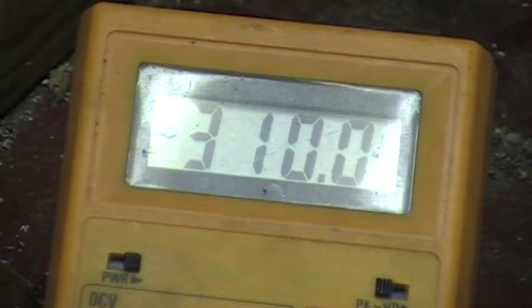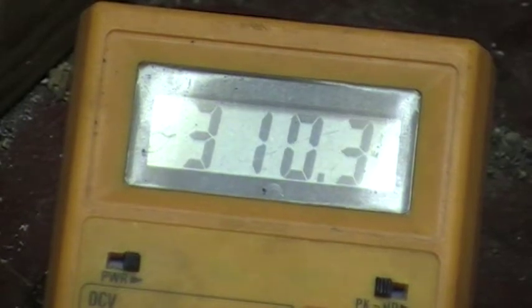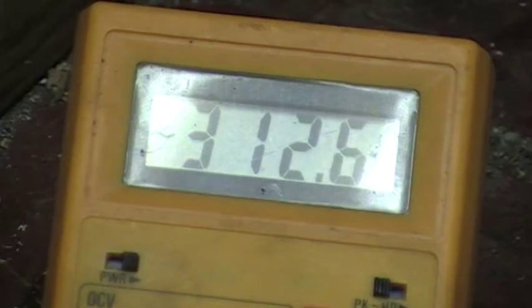Change the wires up here. Now we're going to go to the red and white set of wires, set of coils. Leave it on milliamps and let's read that. We're reading 310, 319, 310, 311. That's good. So she's over 300 milliamps on the red and white coil.